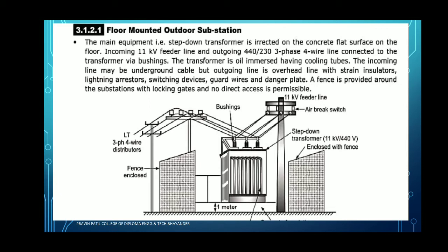The transformer is an oil immersed transformer having cooling tubes. The incoming line may be an underground cable, but the outgoing line is an overhead line with the strain insulator. As shown in the diagram, the strain insulator is also connected. The lightning arrestor, switching device, guard wires and danger plate are connected at the point. A fence is provided around the substation with a locking gate, and no direct access is permissible with the floor mounted outdoor substation.